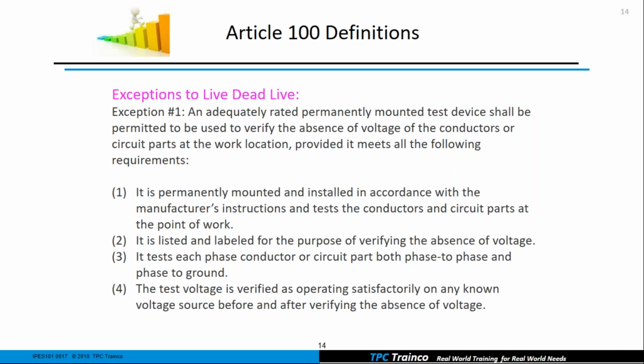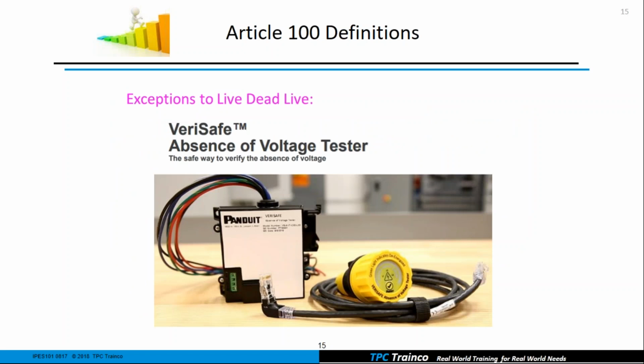So it is permanently mounted and installed in accordance with the manufacturer's instructions. Test the conductors and parts at the point of work, where we're going to be working. Has to be listed and labeled for the purpose of verifying the absence of voltage. It does the same thing that we would do if we were doing it manually. It tests each phase conductor, phase to phase and phase to ground. And the test voltage is verified as operating satisfactorily on any known voltage source before and after verifying the absence of voltage. So basically, this device does the exact same thing that we would do if we were doing it manually. And here's what it looks like.